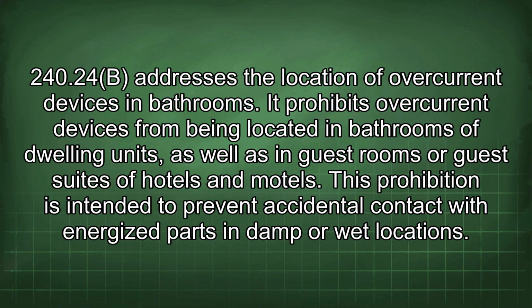240.24(B) addresses the location of overcurrent devices in bathrooms. It prohibits overcurrent devices from being located in bathrooms of dwelling units, as well as in guest rooms or guest suites of hotels and motels. This prohibition is intended to prevent accidental contact with energized parts in damp or wet locations.